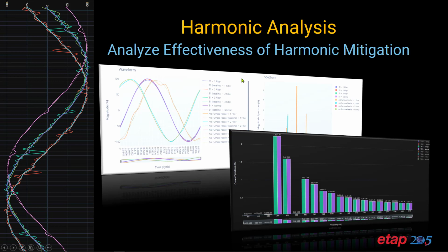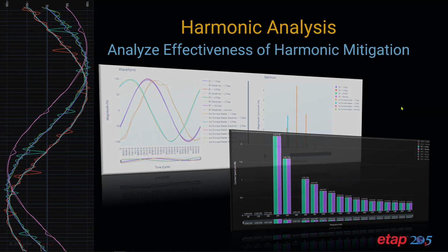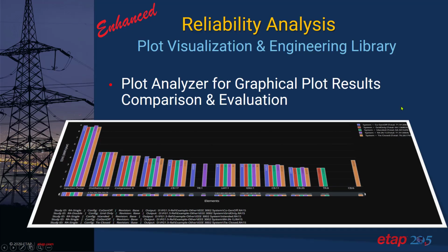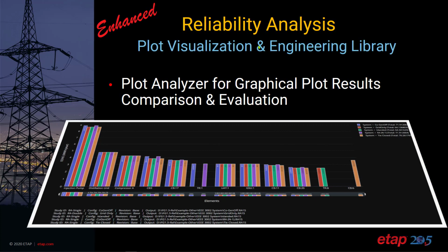A typical application of the plot analyzer for harmonics would be to easily compare a system without harmonic correction, inclusion of passive filters such as single tune filter, bandpass filter, high-pass filter, and understanding the effectiveness of harmonic mitigation in your power system network as seen through a waveform as well as the spectrum. And the spectrum can essentially be overlaid on top of each other across different cases, and you can easily analyze the effectiveness of applying harmonic mitigation methods.